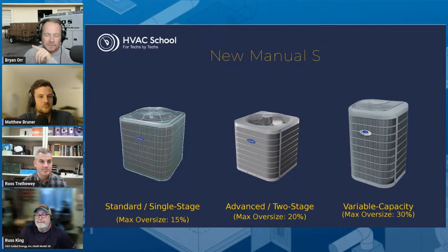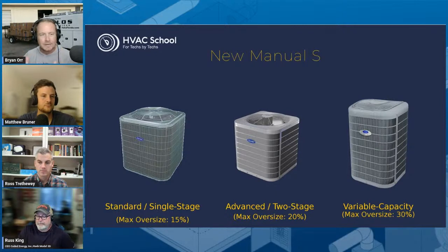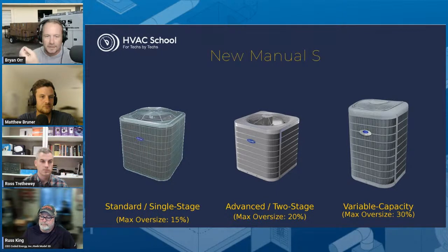Back to a couple things that Ross mentioned. One of the distinctions that I think is really important to make whenever we're talking about this, and I probably should have made it right off the top, is new construction versus the retrofit market or the add-on replacement market. There is a huge difference between those two things. A lot of times when I go to conferences, especially when I'm talking to architects, engineers, designers, they want to have one conversation, which is about ideal situations, what you can build from scratch if you're able to control everything. But the much larger market is the changeout market. And changing a furnace to a heat pump is a risky proposition unless you are paying really close attention to the structure, the envelope, the insulation, the doors and windows, doing a blower door, these kinds of things. Talk about that a little bit, Ross, because obviously you do a mix of both. You do new construction, but you also, it's right in the name of the show, right? You deal with old houses sometimes.